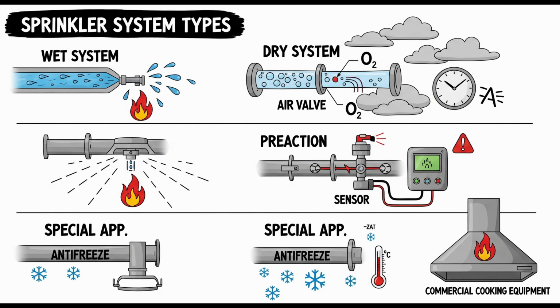Definitely not. For combustible cornices that project more than 12 inches, listed cornice sprinklers are required. They're installed within the bays of the cornice with a maximum 10-foot spacing, and their deflectors positioned about 8 inches below the roof sheathing above. Protecting that overhang. What about roof protection? For roof protection, standard open spray sprinklers, upright, pendant, or sidewall types, are allowed. They are generally installed following the criteria for ordinary hazard group 1 occupancies, with deflectors positioned parallel to the roof slope and about 18 inches above the roof surface. Upright sprinklers located right at the ridge pole of a peaked roof, with horizontal deflectors positioned 6 inches above the ridge, are also permitted, with their spacing and coverage area determined in plan view. All about getting water onto that exterior surface effectively, whether it's a vertical wall, a window, a cornice, or a sloped or flat roof. Exactly.